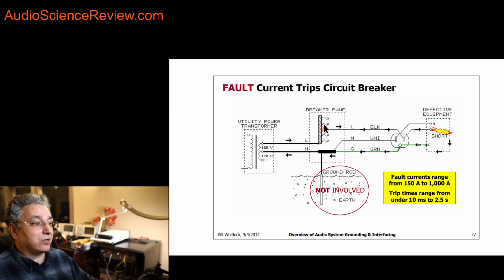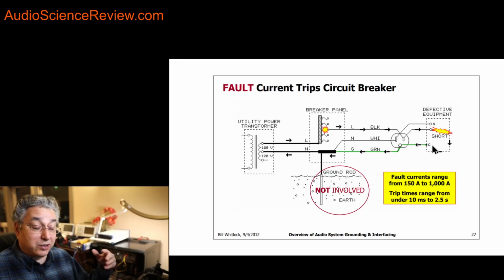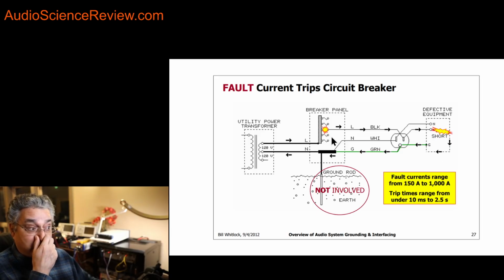And this breaker here, boom, it'll open up. There's a little bit of delay in there, and it will open up. So as soon as this comes loose, connects to the chassis, boom, this disconnects, and the hot wire is no longer hot, and therefore your chassis is no longer hot, and you're not going to get a short. You're not going to get electrocuted. The equipment doesn't work because this has come loose, but we have triggered the breaker to come on.